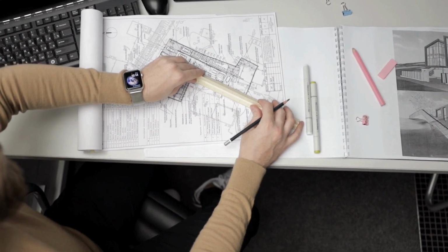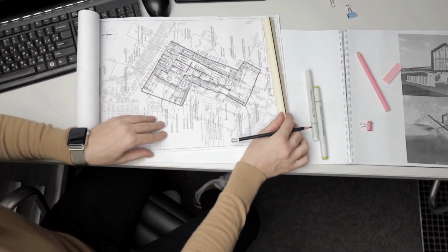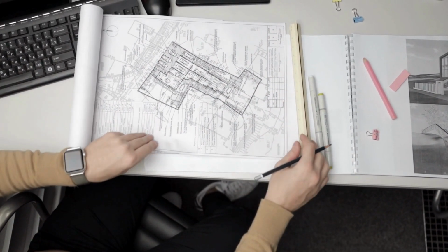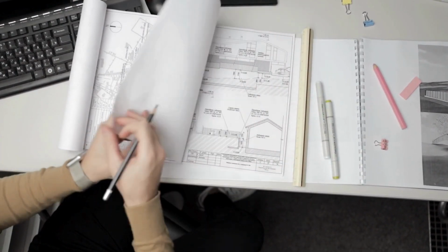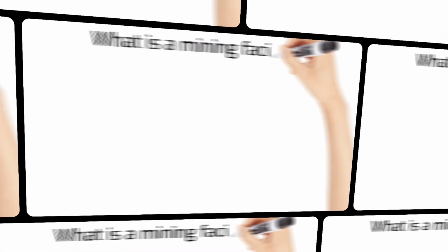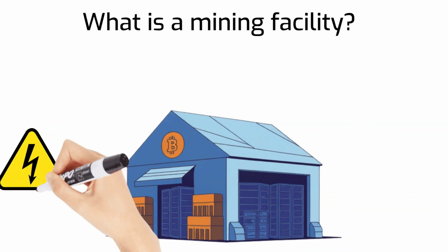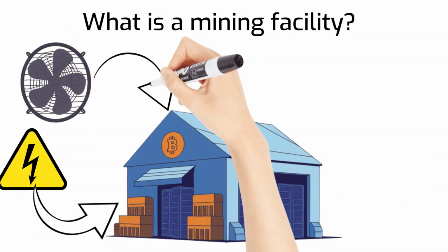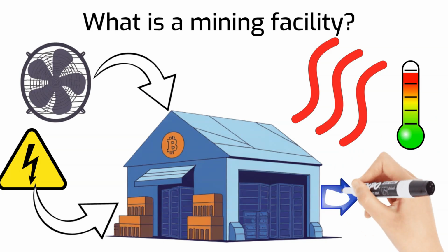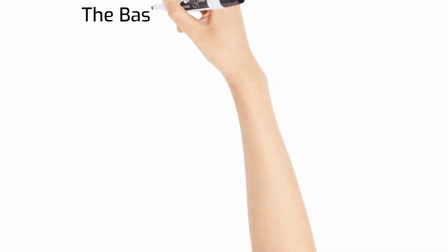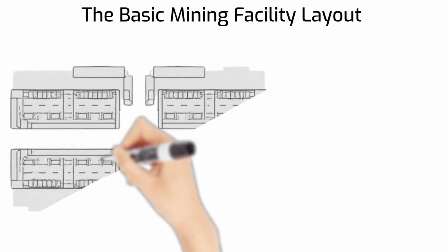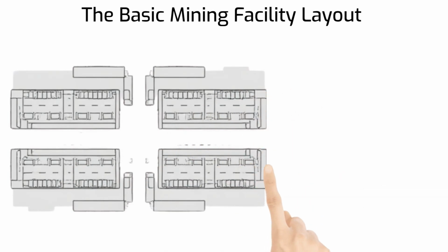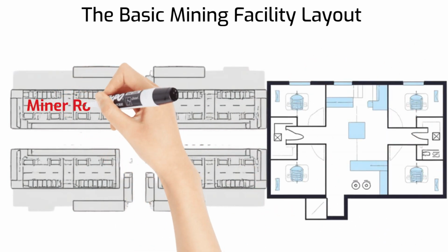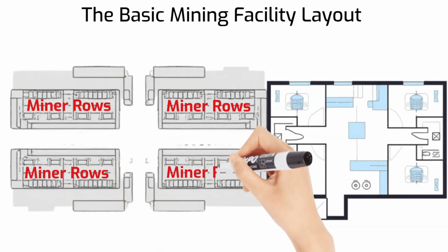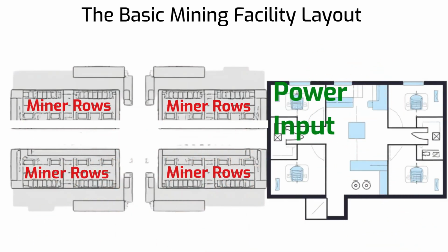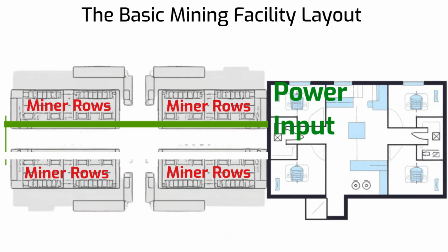At its core, every mining facility follows the same basic layout. Facilities typically use large, open warehouse-type spaces, often pre-engineered metal buildings, to allow for flexible and high-density layouts. Power enters the building, flows to rows of mining machines, heat is removed, and data moves in and out of the network. The most common airflow design for small to medium operations is a wind tunnel approach, where large exhaust fans create negative pressure, pulling cool air in from one side of the building and pushing hot air out the other. Wiring often runs in conduits or is arranged with robust cable management systems.